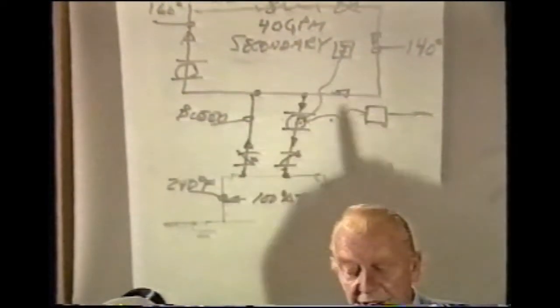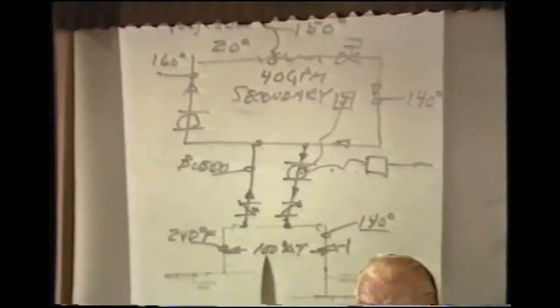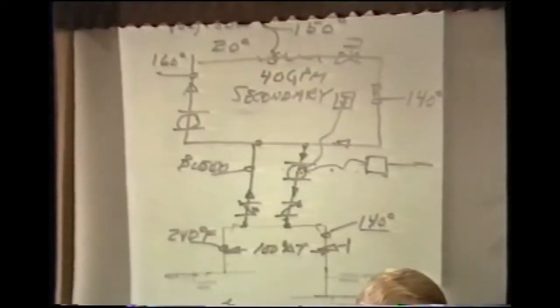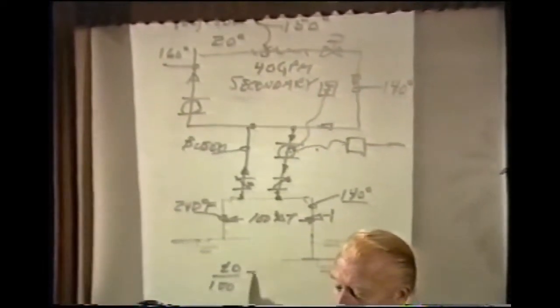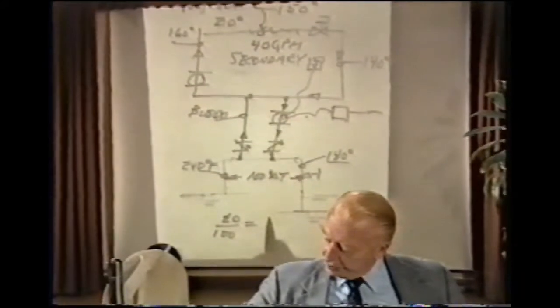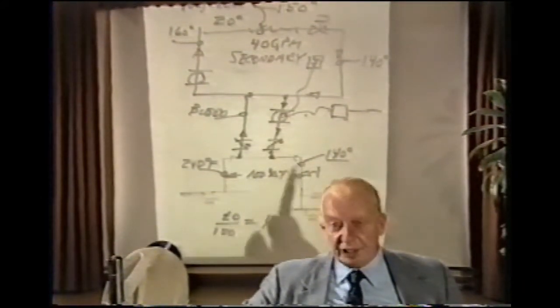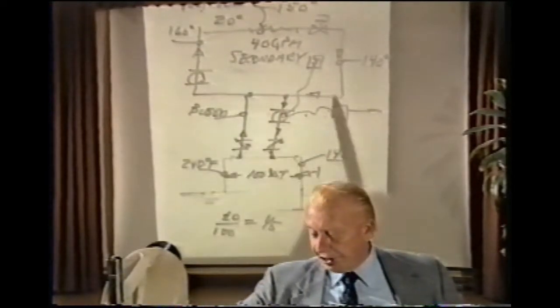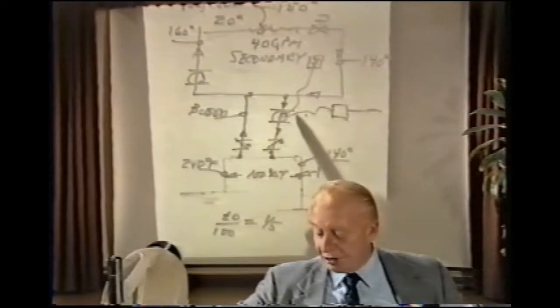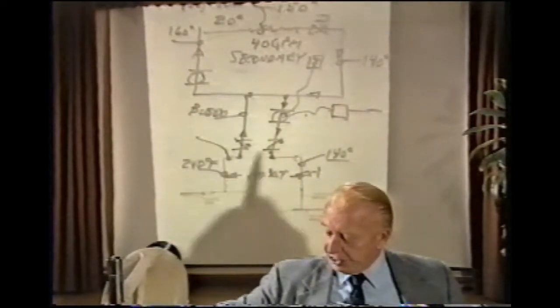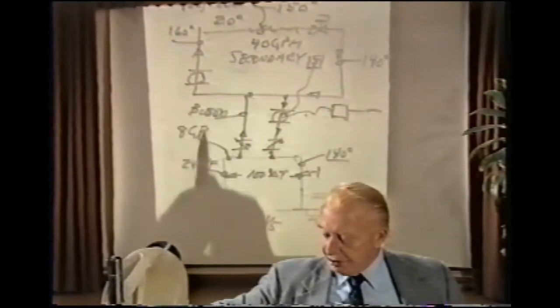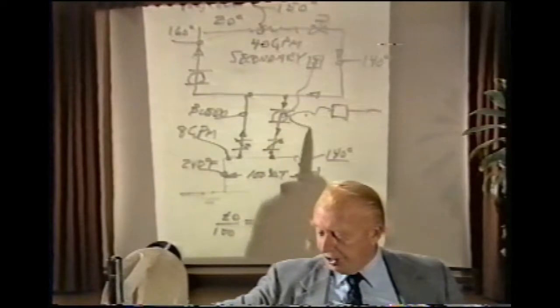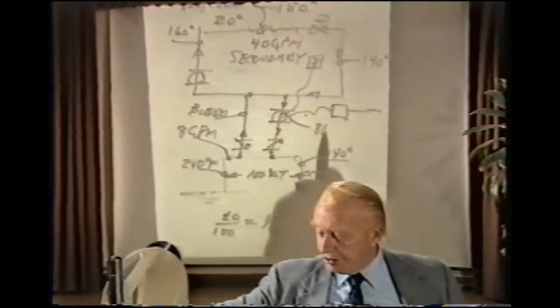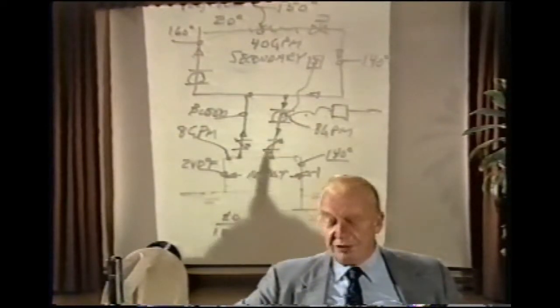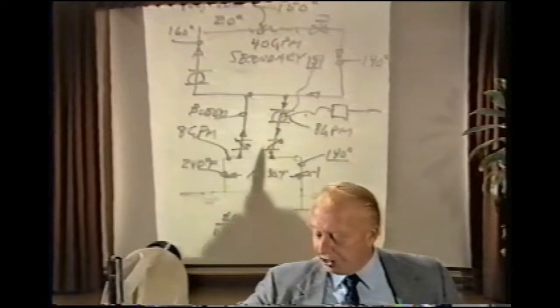We have a 20 degree temperature drop across the secondary circuit. So we need only provide then 20 divided by 100, or 1/5 the flow rate in the primary distribution main that is going to be used in the secondary circuit, and that must be provided by the injection pump. This would mean that our actual need for flow rate is 8 GPM in the primary distribution main, and our pump need only provide 8 GPM in terms of injection pumping when it starts its flow rate.